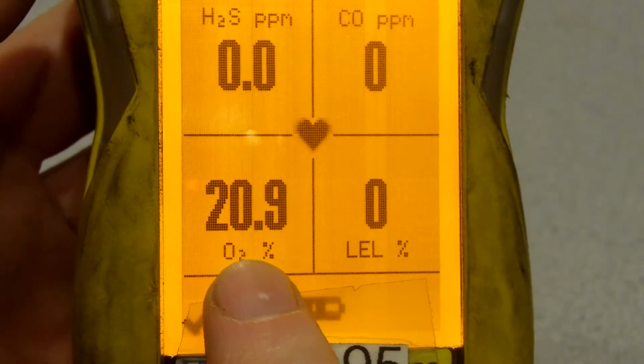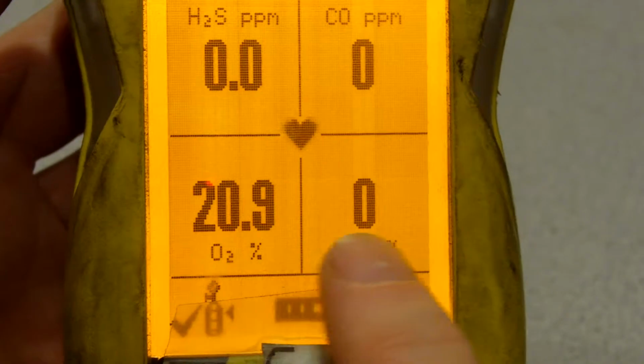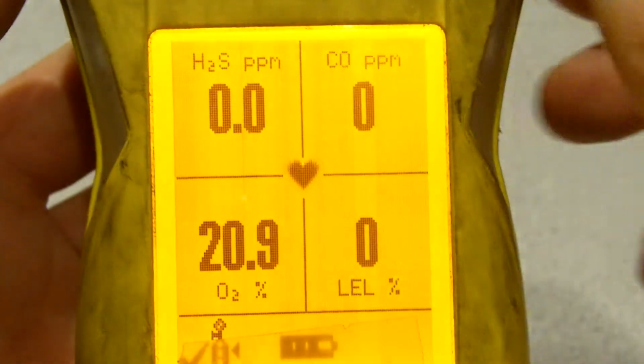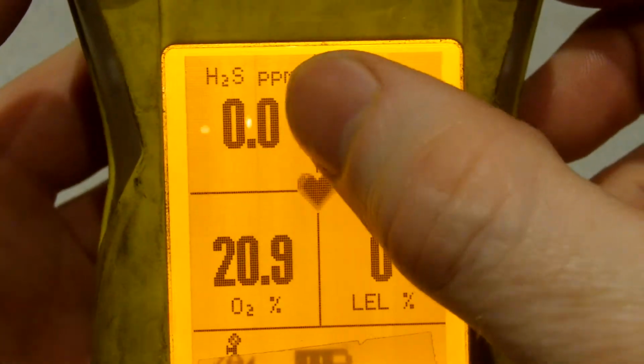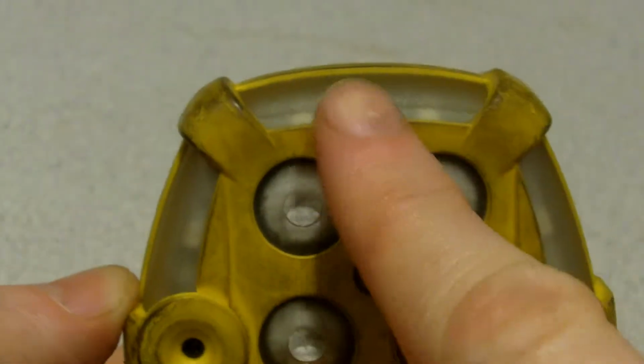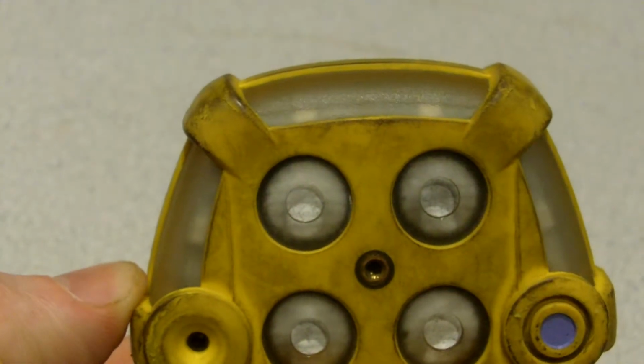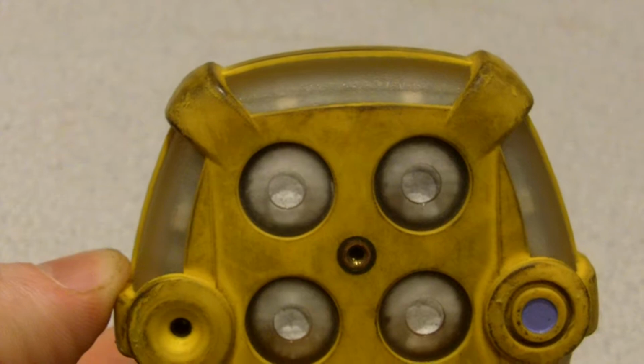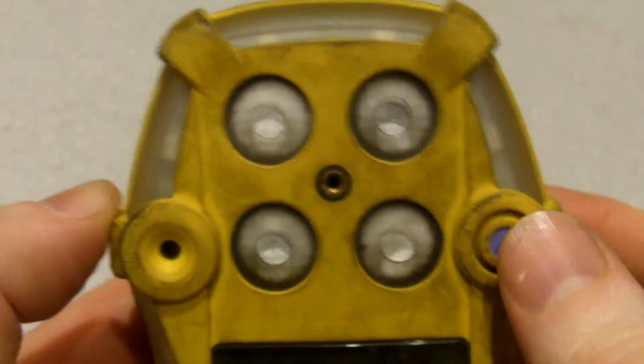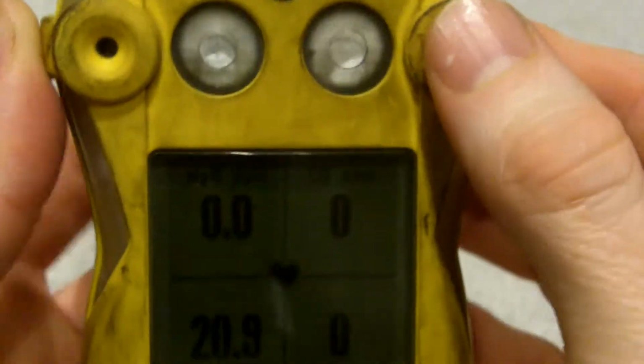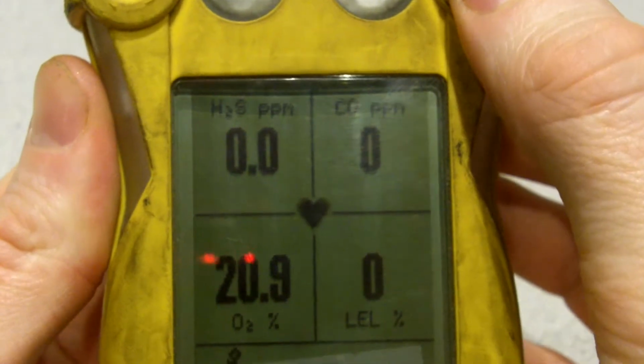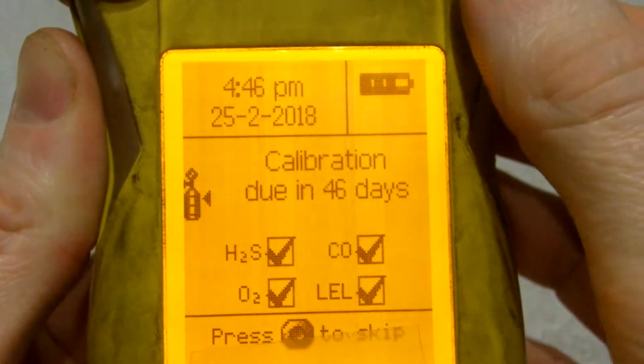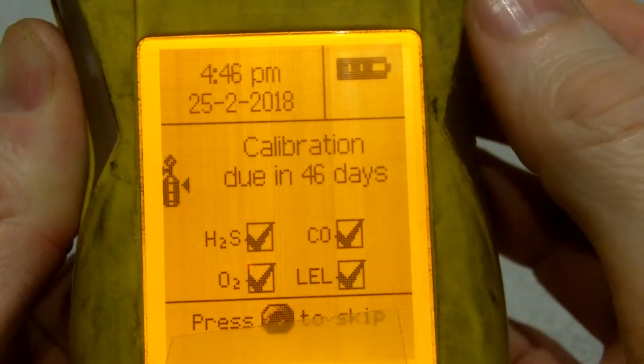Right now I'm reading at 20.9 oxygen, LEL is 0, my CO at 0 and H2S at 0. Also, I have at top a little green light that blinks that indicates that all my checks are okay. From there, if I double click the button rather than a single time, it'll run through its checks to see it says 46 days till it needs to be calibrated again, and all my sensors are good.